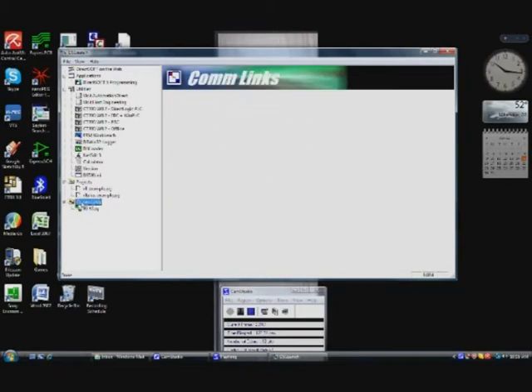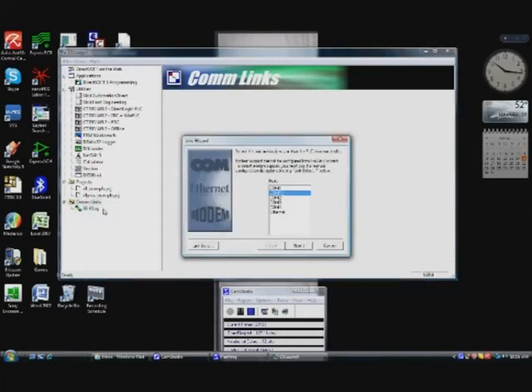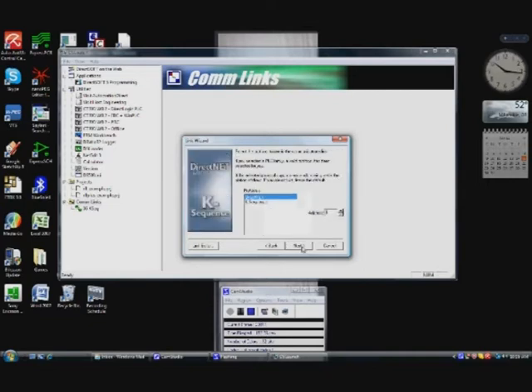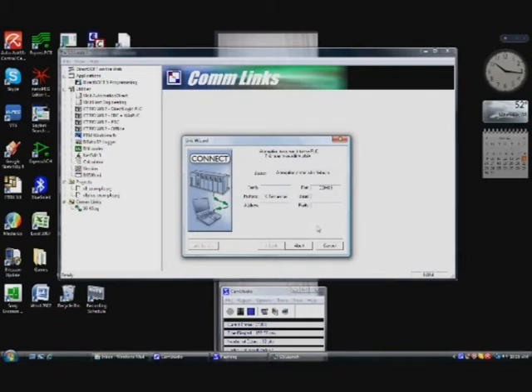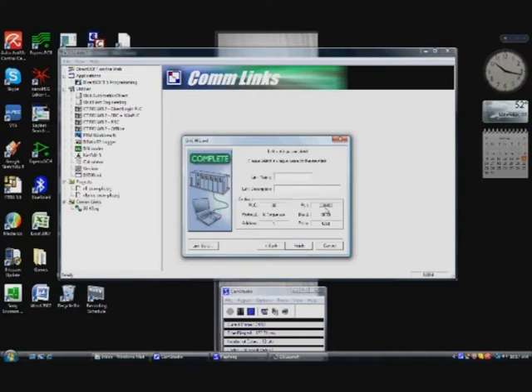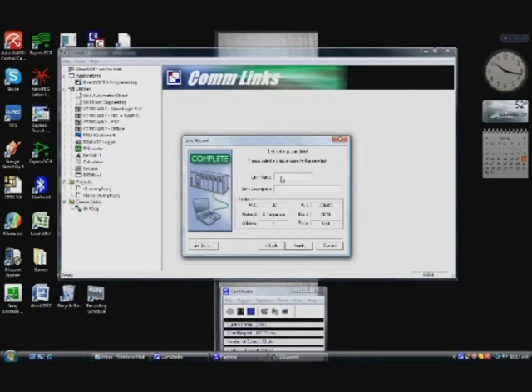You might have to click on add link and select this comm, like in my case comm 13. You can select not sure what type of PLC it is. That works. You want to select k-sequence. Then it tries to communicate with it. It's trying different baud rates, different parities. Now it found it. You would give it a name. You can put any name in here you want. Then click finish. It's going to always show up in here to communicate with it.